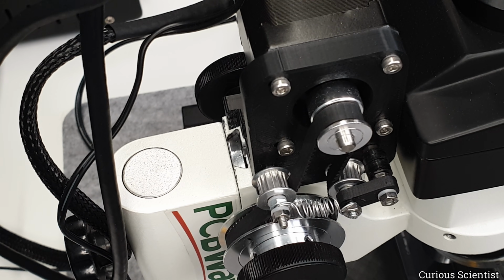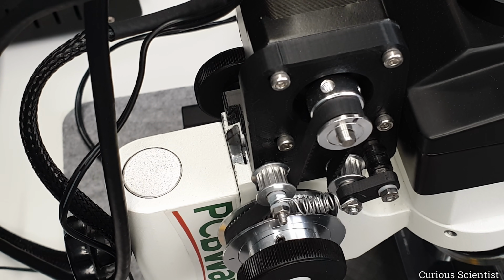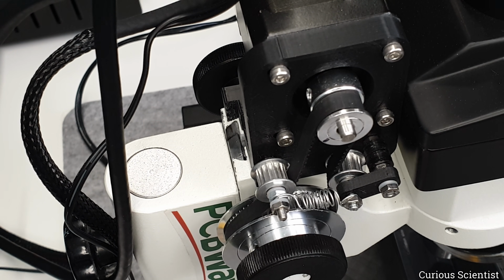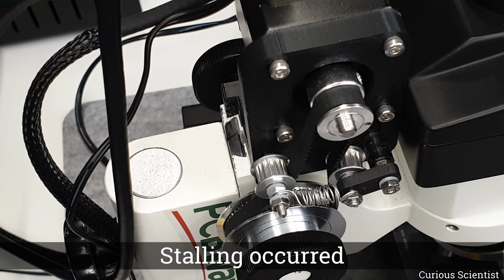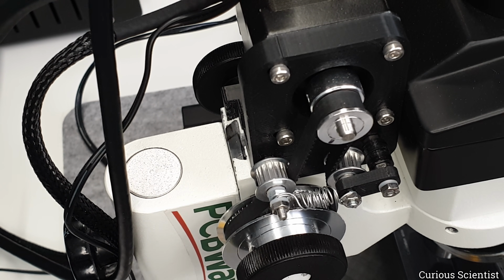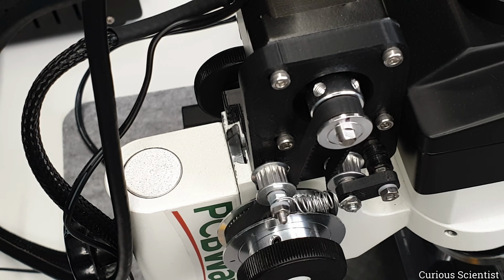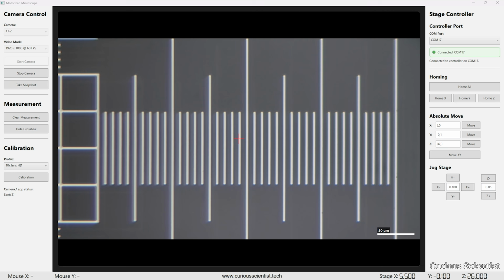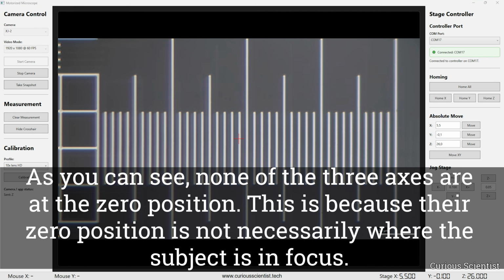When this signal pattern is detected, the motor is stopped, moved back by a certain number of steps, and this position is taken as the 0 position. Then, the motor is driven so that the microscope head travels a little bit down towards the subject. Now, after all 3 axes are initialized, we can move the stage arbitrarily.